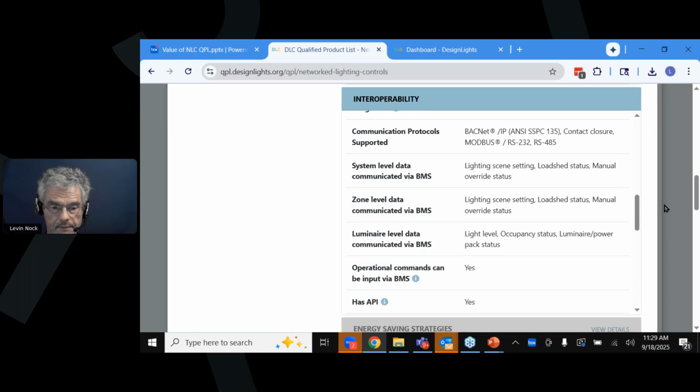So perhaps I'm walking into an owner environment where they need interoperability, but they're not willing to support IP infrastructure. RS-485 is a way of potentially doing that interoperability integration work while not having to rely on an owner network or something of that nature.